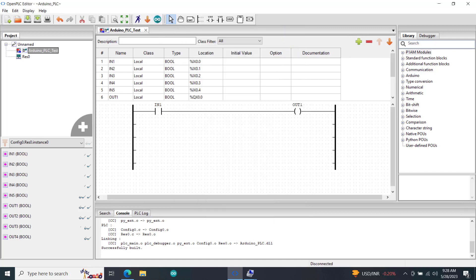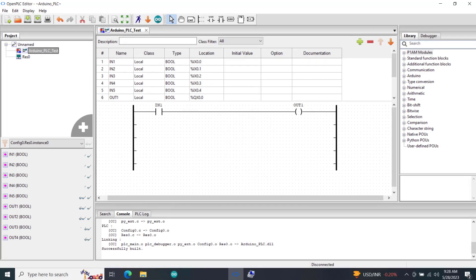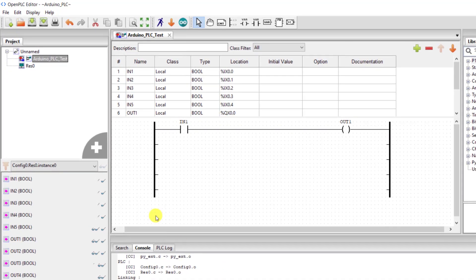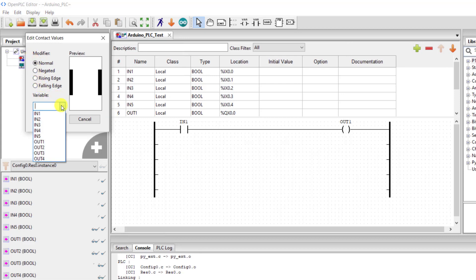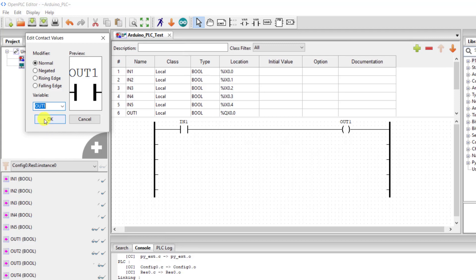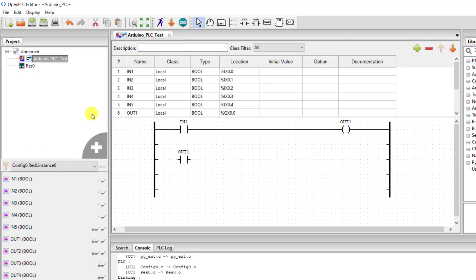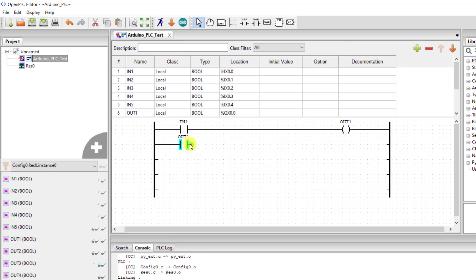Now let's try to introduce latch into our circuit. We quickly add another contact and basically this is going to be the auxiliary contact of our output coil. So we select our output which is output 1 and then we click OK. We position it correctly and then link them to each other. We can see that this contact is parallel to our start button.